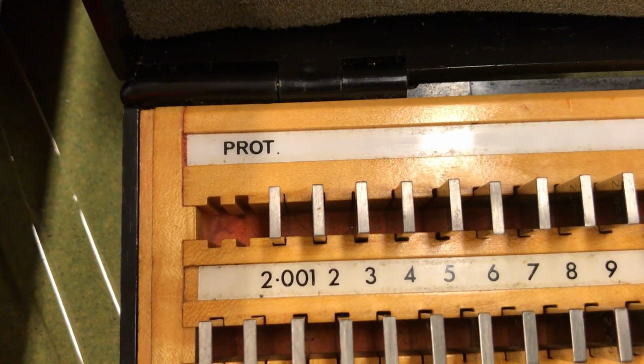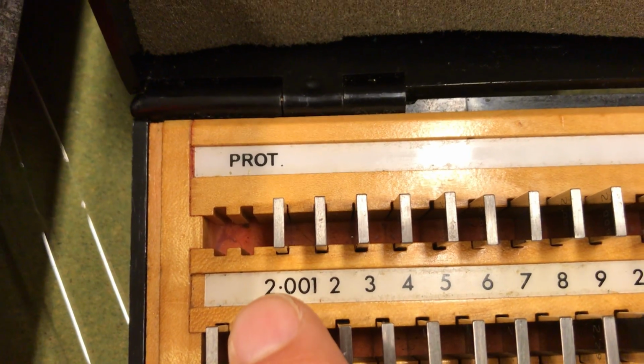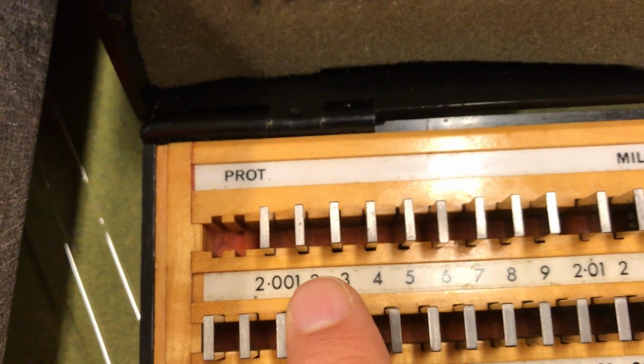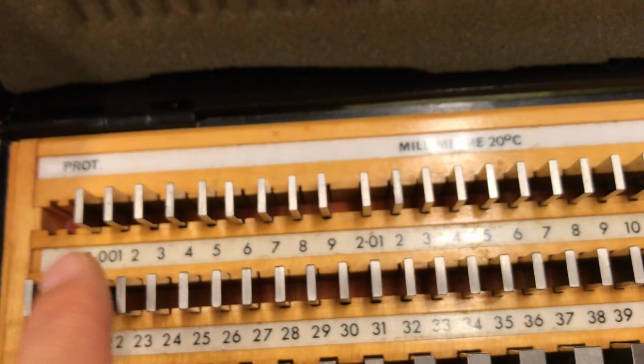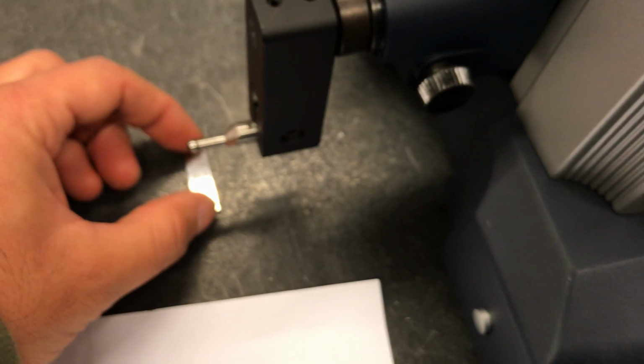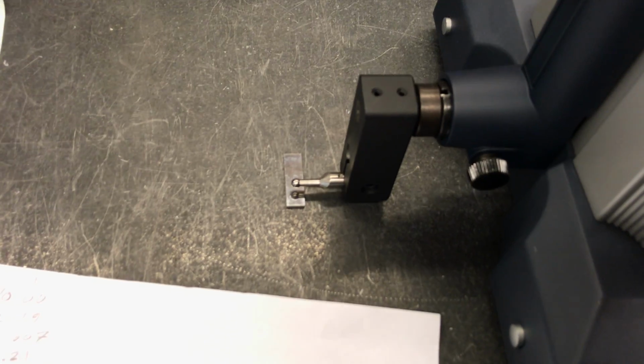I hope you can have a good look at this one. It is 2 millimeters and 0.01 millimeter, 0.001, so it's 1 in thousandths of millimeters. I'm going to take this specimen and try to do the calibration with it. I don't expect we're going to have the full accuracy for this machine, not because the machine is not accurate, but because the table has a problem, and we're going to talk about what the possible problem is for this table. So I put it exactly under the probe.